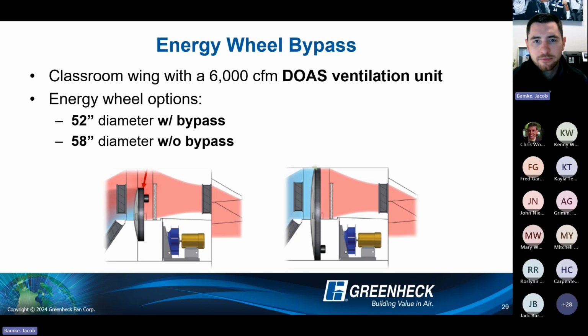We're going to focus specifically on wheel bypass. In this example, we have a classroom wing. It's 6,000 CFM. It's a true DOAS ventilation unit. There's really two options that you would see. One, you would have a 52-inch diameter with bypass, which you can see on the left. You have to shrink it down to fit this bypass damper in. And then the second one is you could size that wheel as large as possible, but in those situations, you couldn't fit a bypass damper. So now you have to make sure that you have some other control strategy in place.